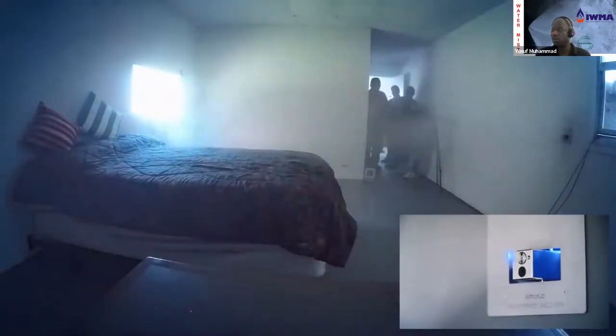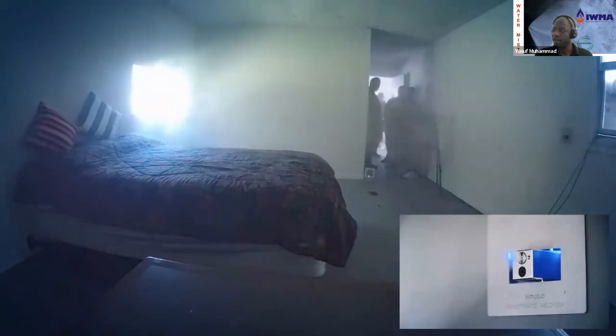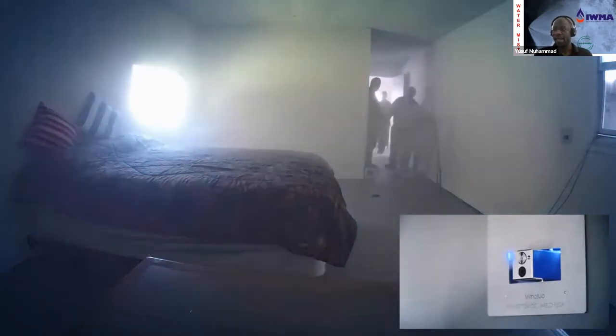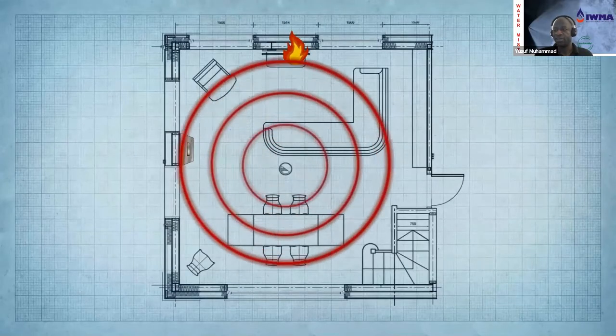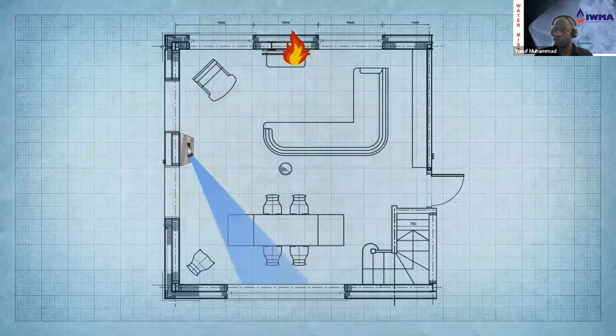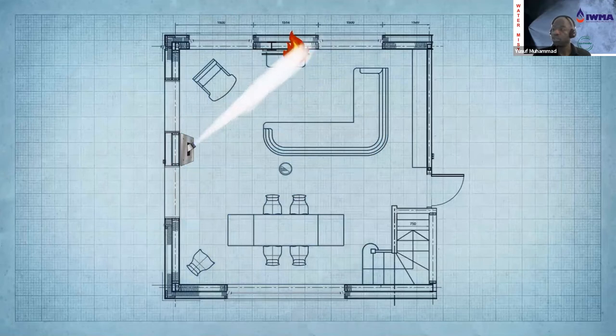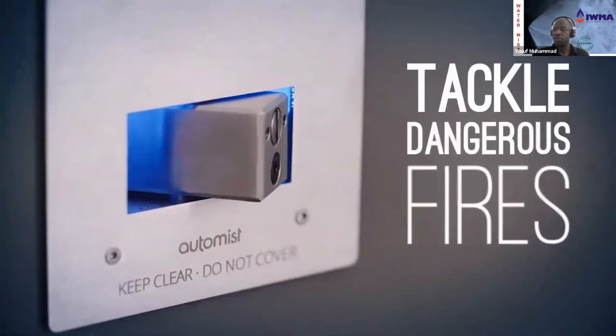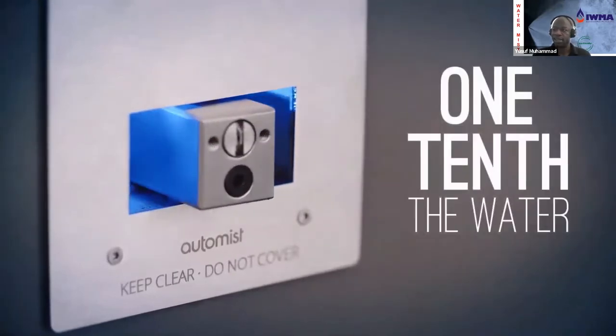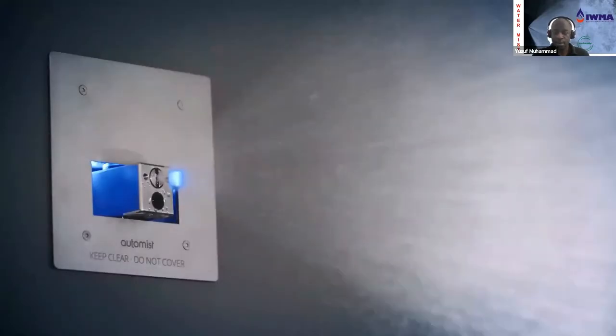Now, our system is unique in its approach. What we do is we mount our nozzles lower down on the wall, about light switch height, and we target the fire specifically. So we have an initial trigger, which is your early warning alarm. We then scan the room through 180 degrees, and then we target the fire's location with a blade of water mist. And this approach means we can use 10 times less water than a traditional sprinkler.